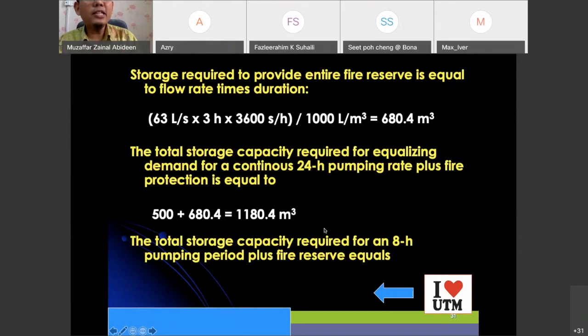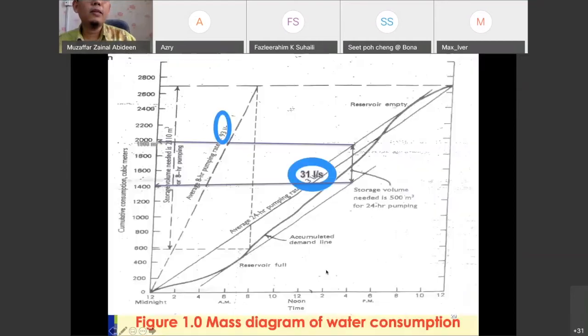The fire reserve is still the same, it's still 680.4 so we do not have problems on that. But now for the second part of the question, they only switch on for eight hours. What it means, instead of pumping the water for 24 hours, and that's why we have this pumping rate at 31 liter per second, they will only switch on the pump for eight hours.